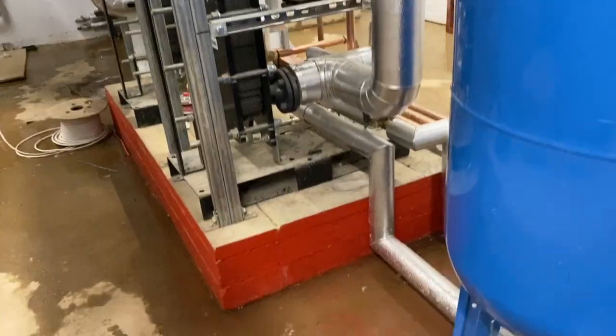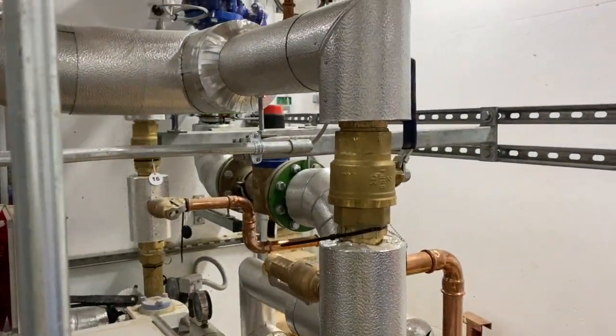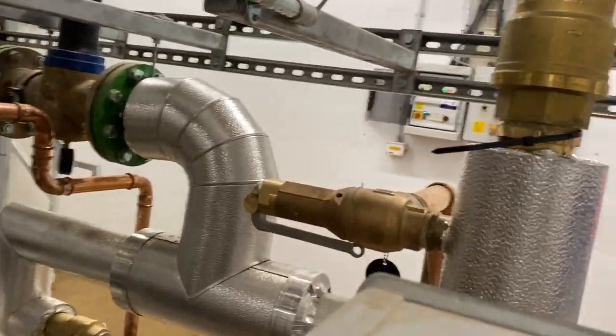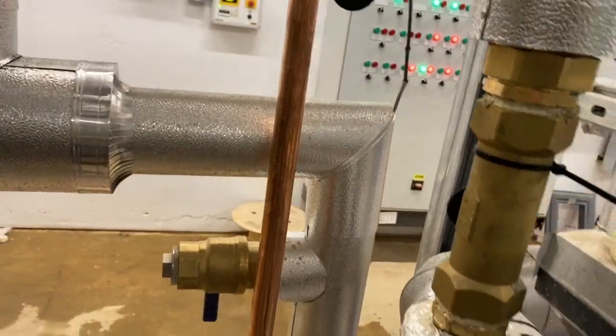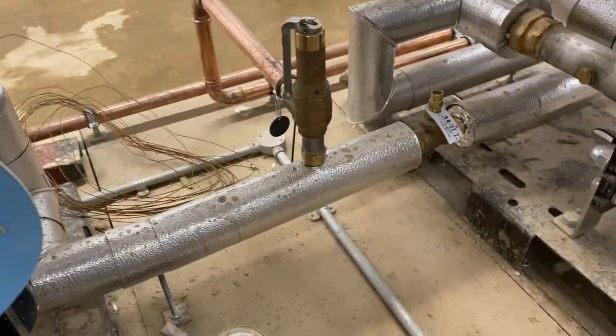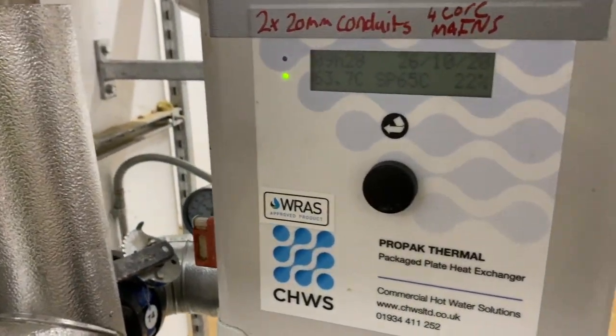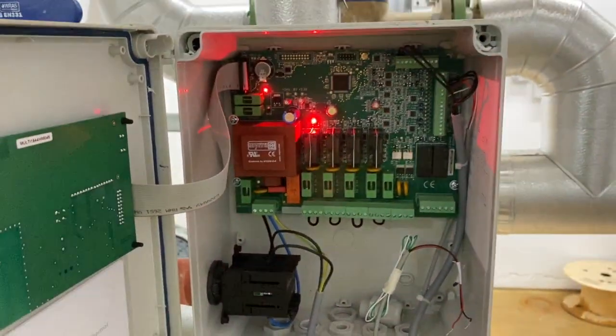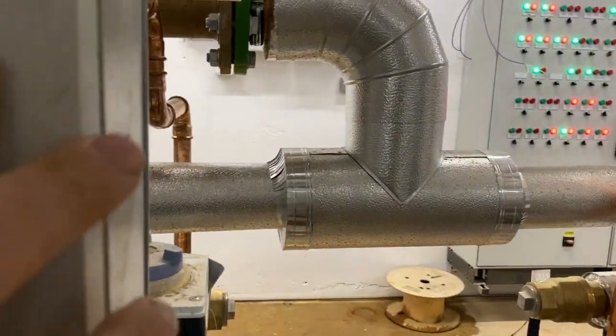Just various tappings here available on the tanks. Back around to a plate, 2-port valve, isolation valve. Again, that non-return on the outlet, not typically there. Everything done off the front panel. Again, this is the top section, is where the demand from the central heating, from the BMS, beg your pardon. On the top right hand corner and the bottom right hand corner is the alarms. The electrical, the map is on the right hand side of the unit.